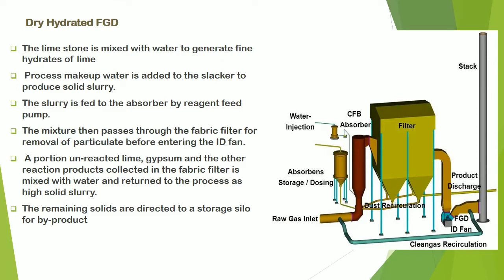Dry Hydrated FGD: the limestone is mixed with water to generate hydrated lime. Processed makeup water is added to the slaker to produce solid slurry. The slurry is fed into the absorber by a reagent feed pump. The mixture then passes through a fabric filter or ESP for removal of particulate matter before entering the ID fan. A portion of unreacted lime, gypsum and other reaction products collected in the fabric filter is mixed with water and returned to the recirculation system as high solid slurry. The remaining solids are directed to a storage silo as a by-product, and clean gas exits from the stack.